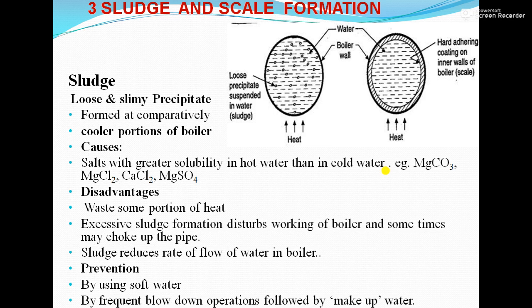How can we overcome sludge? First, by using soft water — we have to treat the boiler water outside the boiler by external treatment. Second, by frequent blow down operation followed by makeup of water. In blow down operation, we replace the residue water containing a large amount of sludge with fresh water.